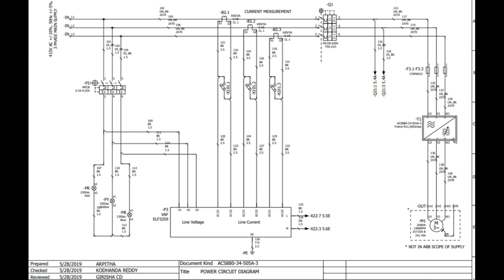Going ahead, we can see the fuses on the most right hand side, F3.1 to F3.3, and the rating is also provided, 170. And further, after the fuse, the main supply will hit our drive, that is U1, V1 and W1. That is the input terminals of the drive. And after this, AC is converted into DC and further into AC, that is variable AC. Here we can see the output from the drive, that is U2, V2, W2, will finally feed the motor, and the motor will run according to the reference given. Next we'll come to another page.